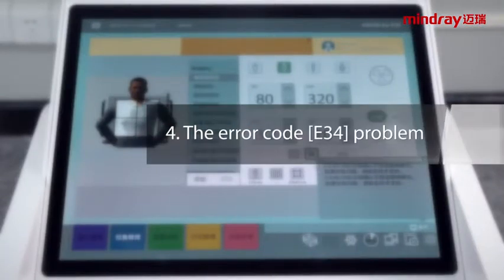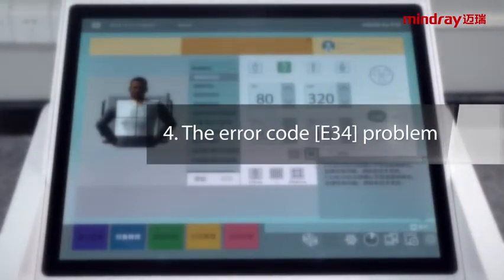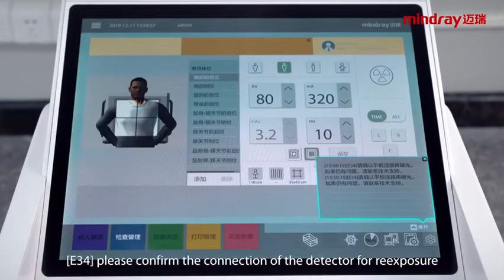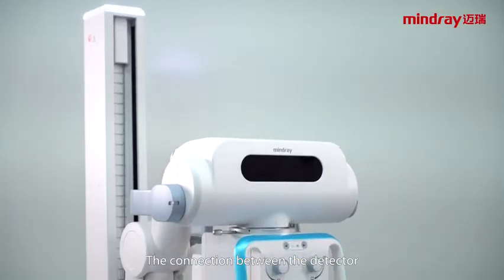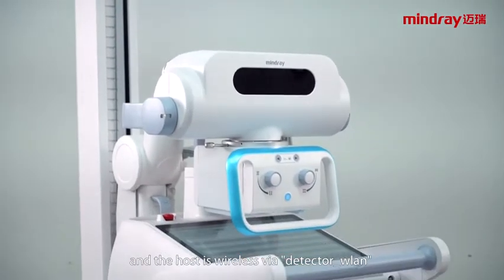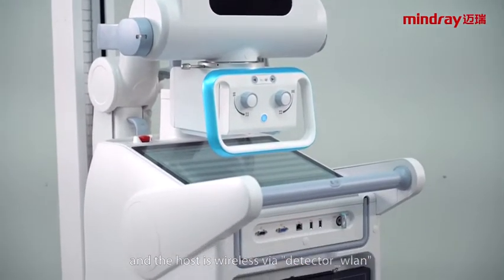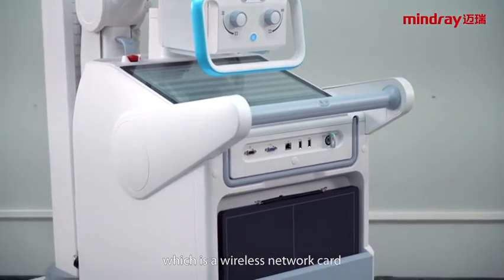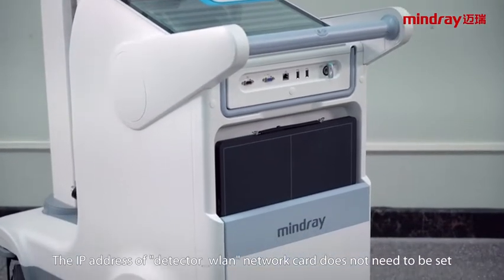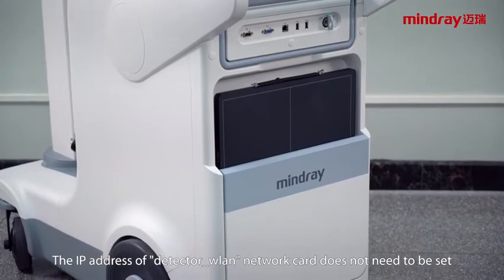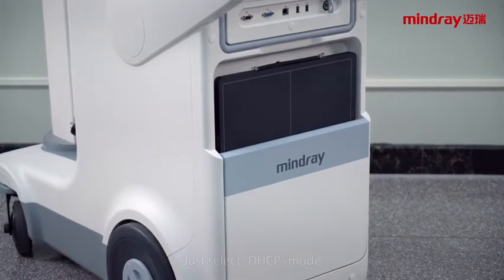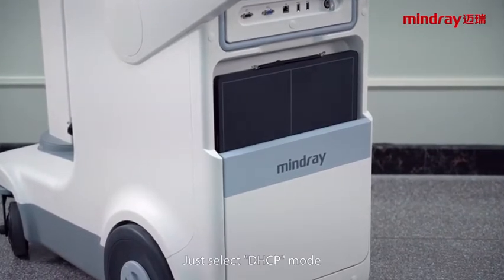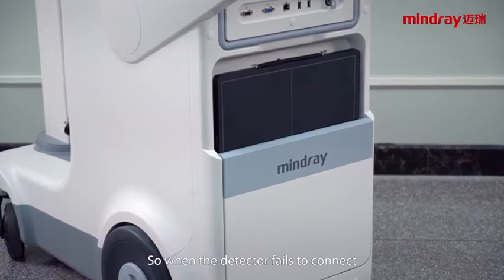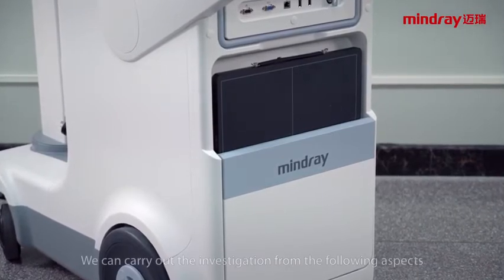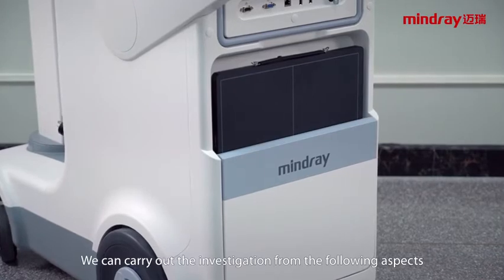The machine reported an error during exposure. Please confirm the connection of the detector for exposure. The connection between the detector and the host is wireless via Detector WLAN, which is a wireless network card. The IP address of the Detector WLAN network card does not need to be set. Just select DHCP mode.